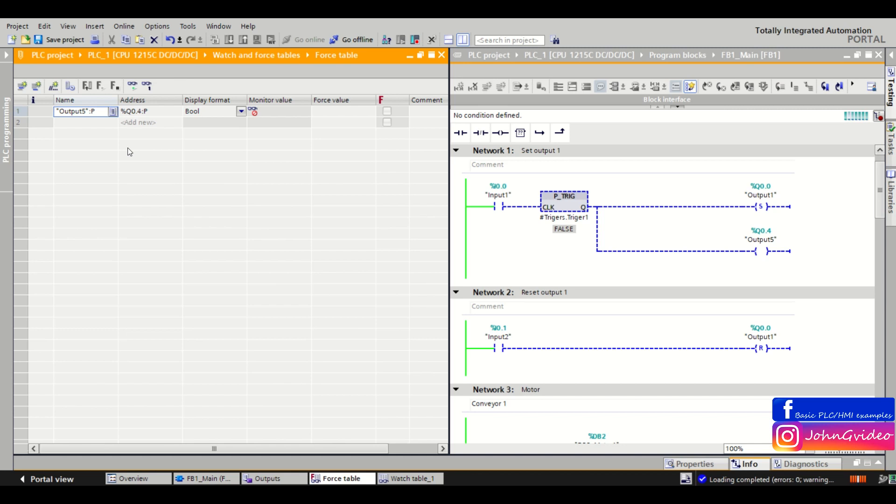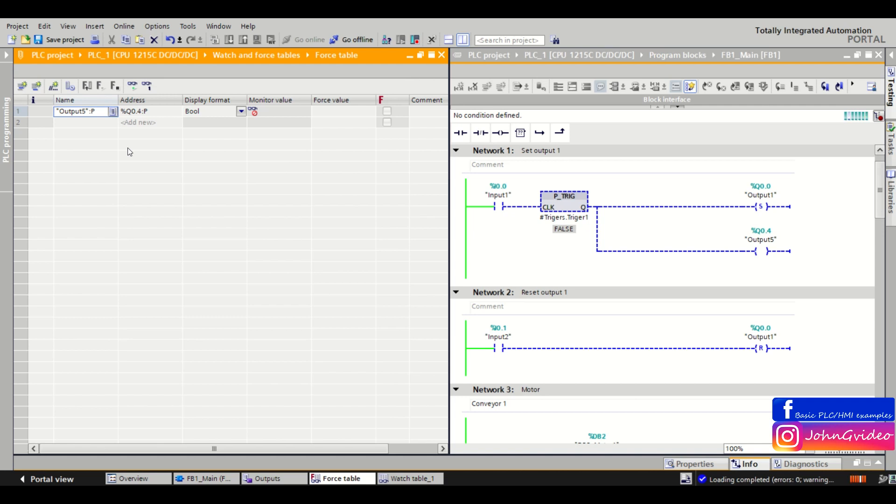Also when we go to the forcing of the variables and for example we force some variable to true and then we lost the connection with the PLC, obviously the forcing is still active in the PLC. And when you use the watch table, watch table is active only when you are connected with the PLC from the PC and you are online.